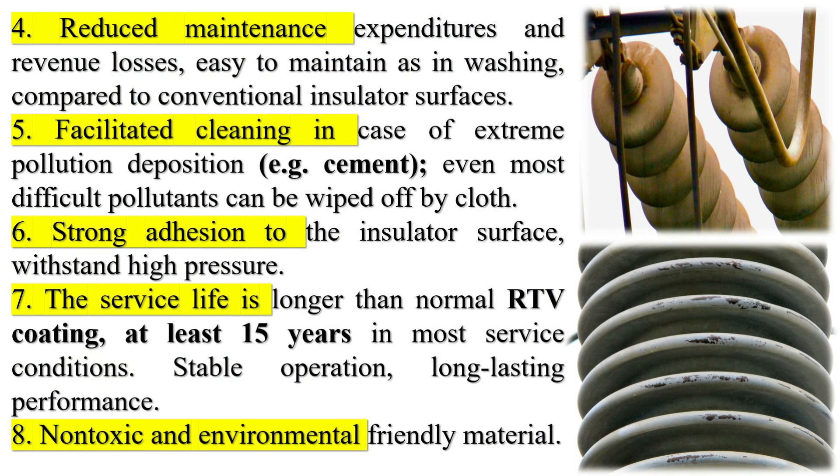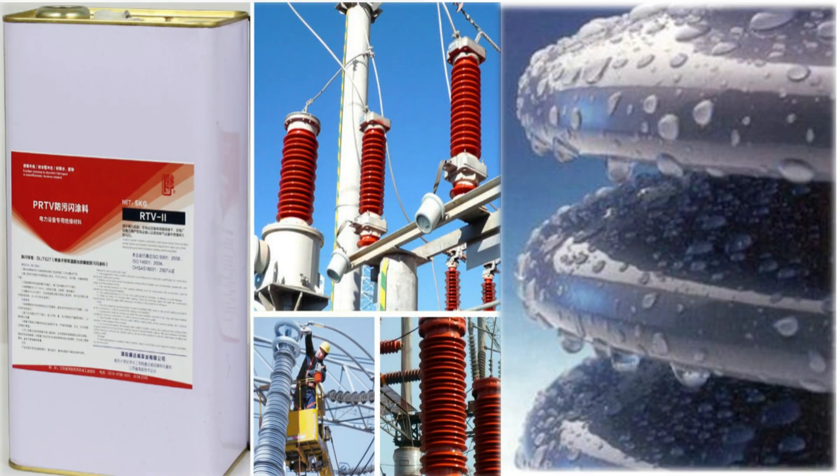The performance of the insulators coated with RTV under partial coating damage and undamaged coating was evaluated. The results showed that the flashover characteristics of the RTV-coated insulators had a significant difference compared to normal insulators. Electrical characteristics such as flashover voltage, critical current, and surface resistance were significantly affected by coating damage distribution and humidity level on the insulator's surface.